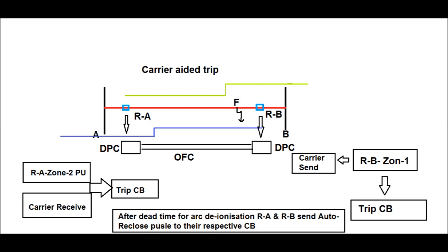Since relay A has zone 2 pickup and carrier received, it will trip the circuit breaker. That is, AND logic is incorporated for the relay at the A end: zone 2 pickup and carrier received, it trips the circuit breaker at zone 1 time. Since both circuit breakers trip simultaneously, after a dead time for arc deionization of the fault, the relay at the A end and the relay at the B end send an autoreclose pulse from their respective distance relays to the circuit breakers to normalize the feeder.